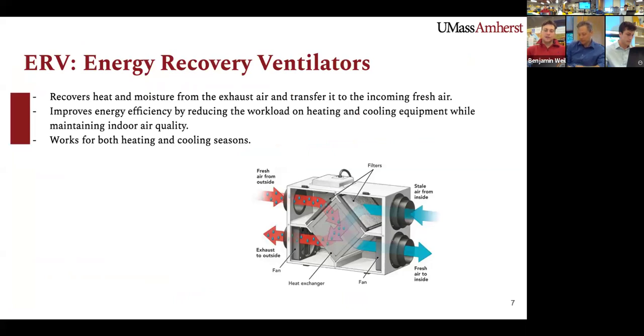An energy recovery ventilator, otherwise known as an ERV, is a system that helps maintain indoor air quality while improving energy efficiency. How an ERV works is it has two vents, one for intake, bringing the fresh air in, and one for exhaust, pushing stale air out. Inside the ERV, there is a heat exchanger that allows the incoming fresh air and outgoing stale air to pass close to each other without mixing. This system captures the heat or coolness from the outgoing air and transfers it to the incoming air. By recovering heat or coolness from the outgoing air, the ERV reduces the workload on your heating and cooling systems. This results in lower energy consumption and reduced energy bills while still maintaining a comfortable indoor environment.